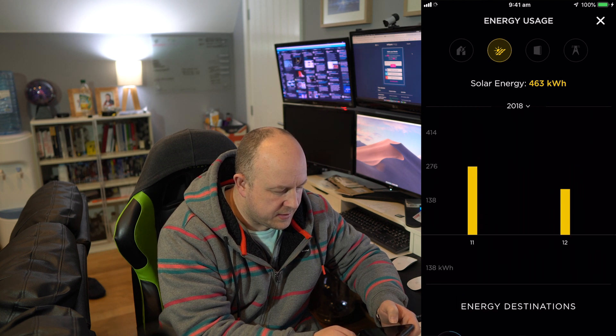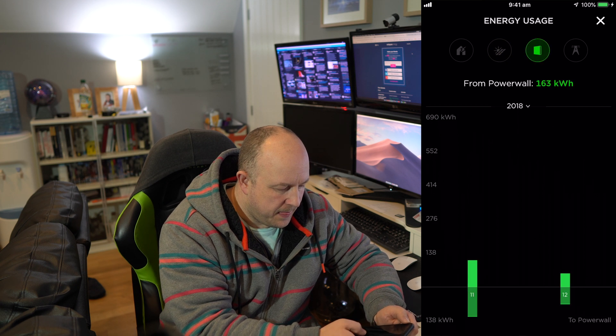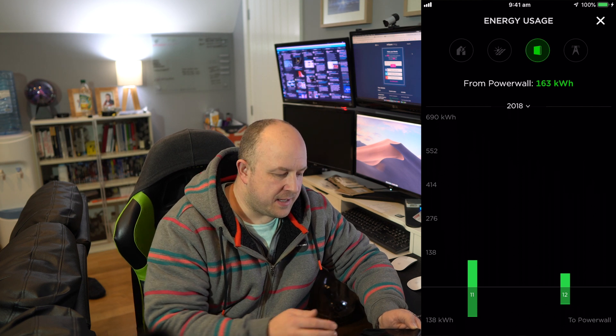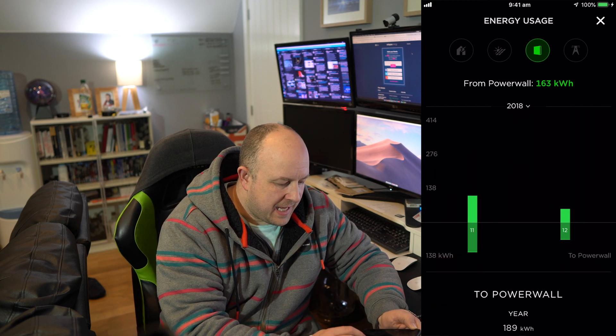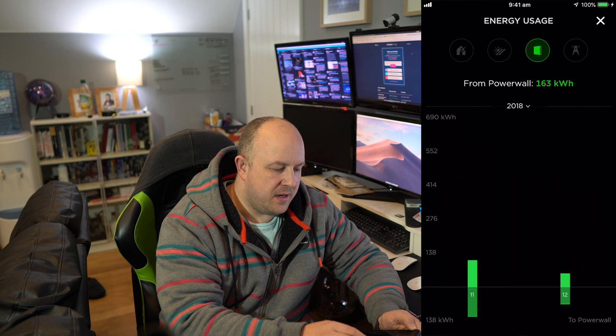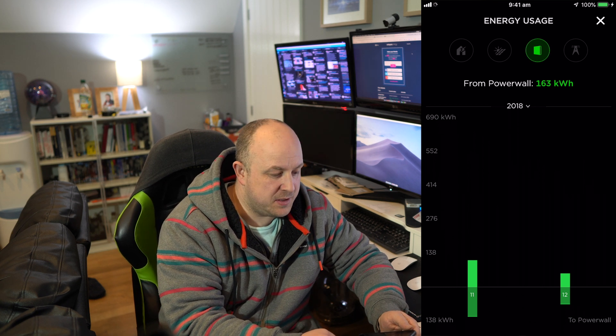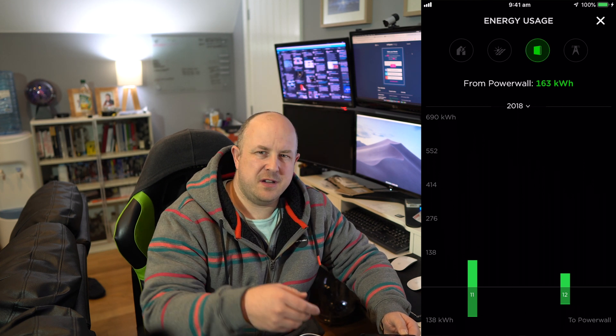So there are some cool little things on here. If we look at the Powerwall, we have a bit more information. We can see from when the Powerwall was installed — the 1st of October through to the end of December — the Powerwall had 189 kilowatts of solar go into it, and from there I was able to consume 163 kilowatts. So that's around 86% efficiency. Tesla say it should be 90% efficient, but mine has worked out over the quarter to be about 86% efficient, which I think is still good. I'm not sure if the hit on efficiency is due to heat and cycling.